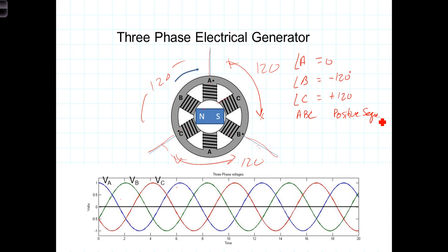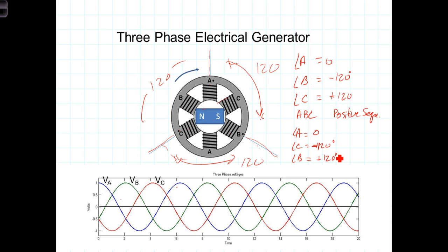On the other hand, if as we're assigning the letters, the A phase is at zero and directly following the A phase we have the C phase at minus 120 degrees, and then the B phase coming along at positive 120 degrees relative to A, that is referred to as an ACB sequence or a negative sequence. This is specified by the power company when electricians are hooking things up — they need to know which phase is leading and which is lagging. Get them backwards and your motor will actually turn in the opposite direction.